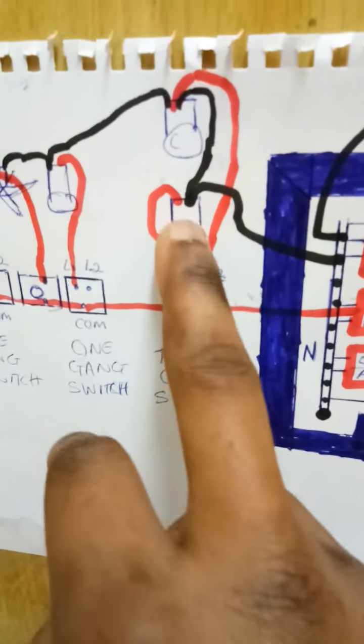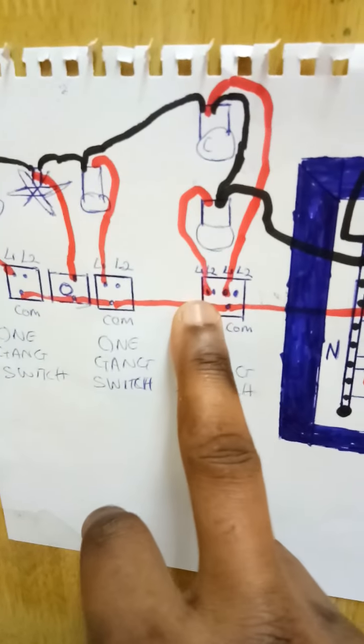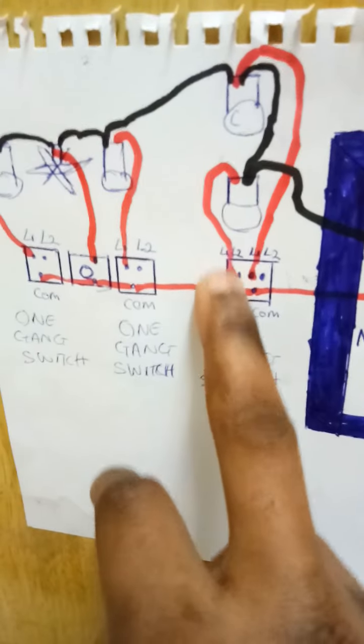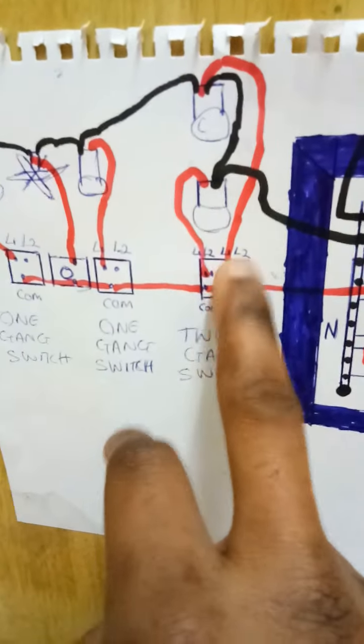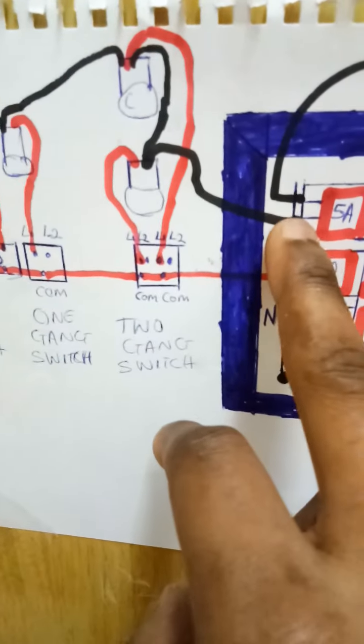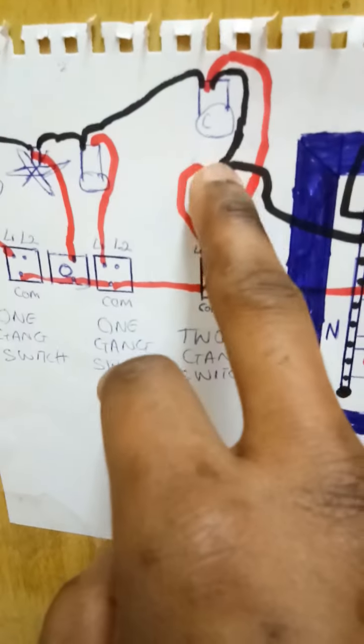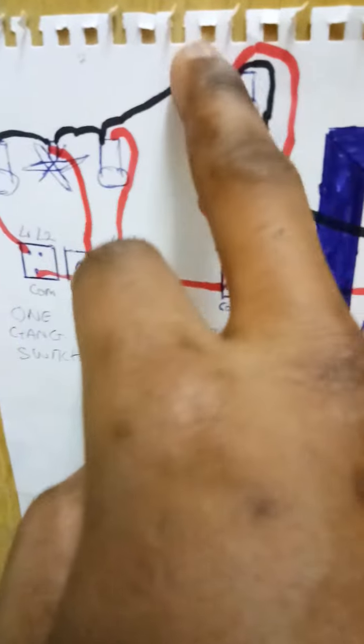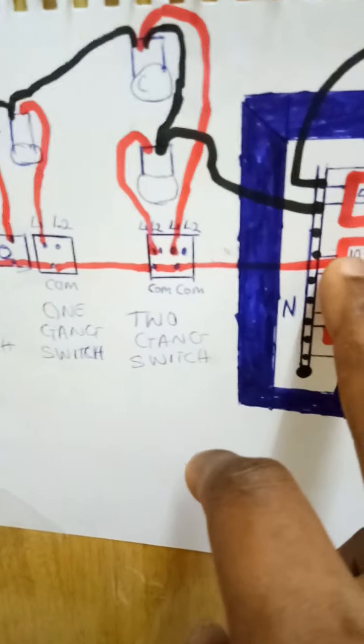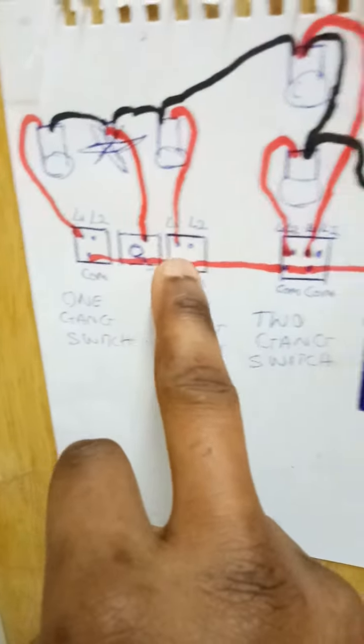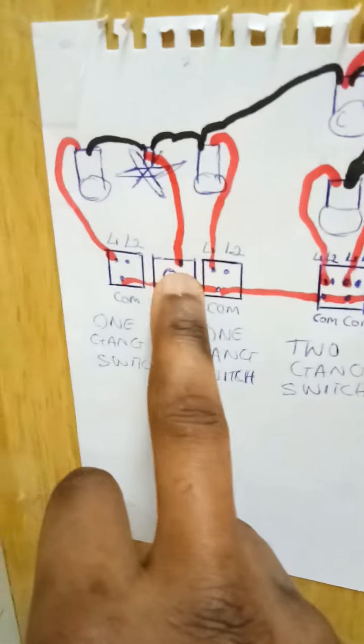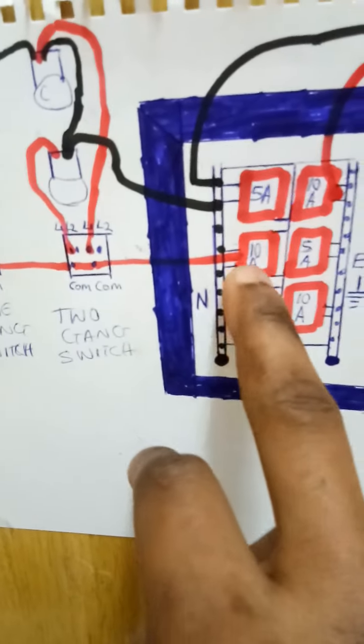As you can see here, this lighting point is also 1-gang. This is a 2-gang switch. This gang controls this lighting point. The second gang controls this lighting point. All the neutral comes from the copper bar and joins together. All the neutrals are connected together, but the supply from the circuit breaker comes to the switches. This is another circuit, because when you cut off this supply from here, all these lighting points and this one will be cut off, whereas this one will be working.